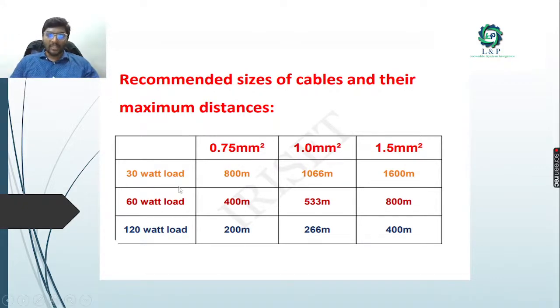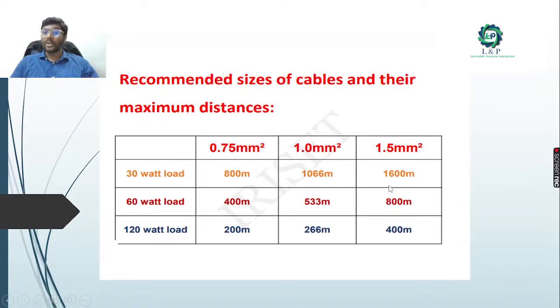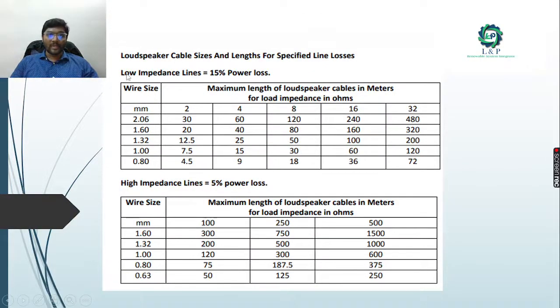Recommended cable sizes: for a 30-watt load, 0.75 mm² cable can be used up to 800 meters, 1 mm² up to 1066 meters, and 1.5 mm² up to 1600 meters. For 60 watts: 400 meters, 533 meters, and 800 meters respectively. For 120 watts: 200 meters, 266 meters, and 400 meters. If you know the wire size, maximum length, and load impedance, you can calculate power losses. This shows how to determine maximum wire length for a particular wire size.